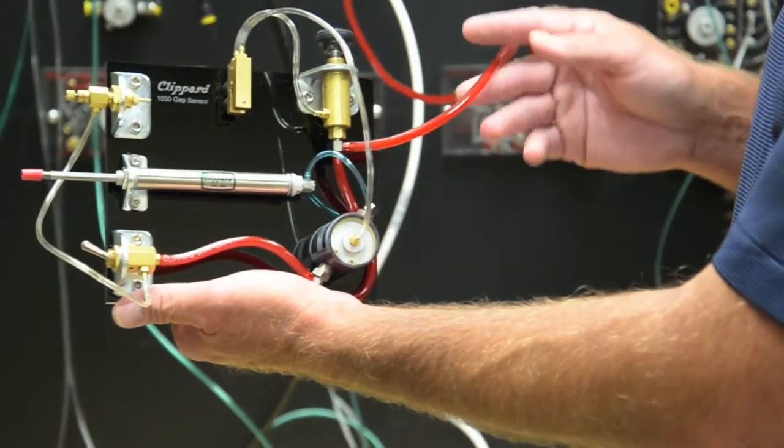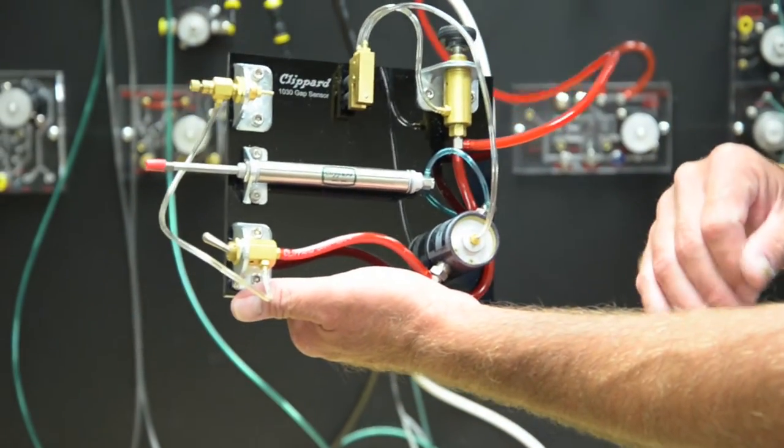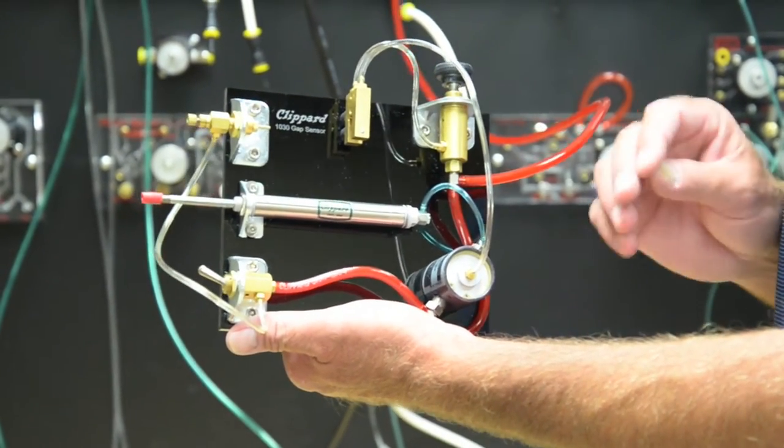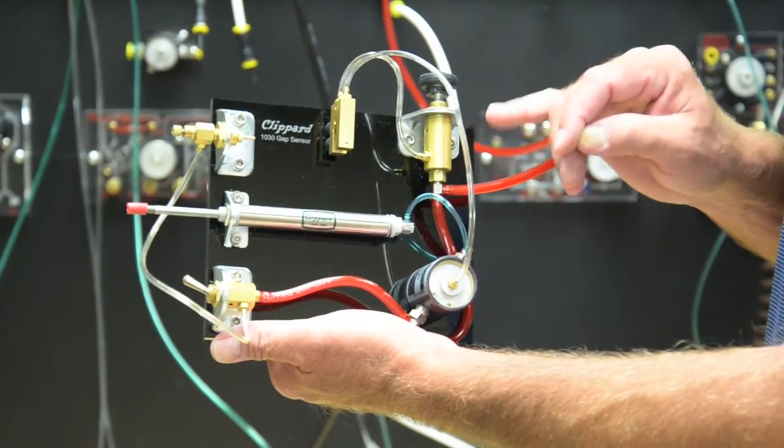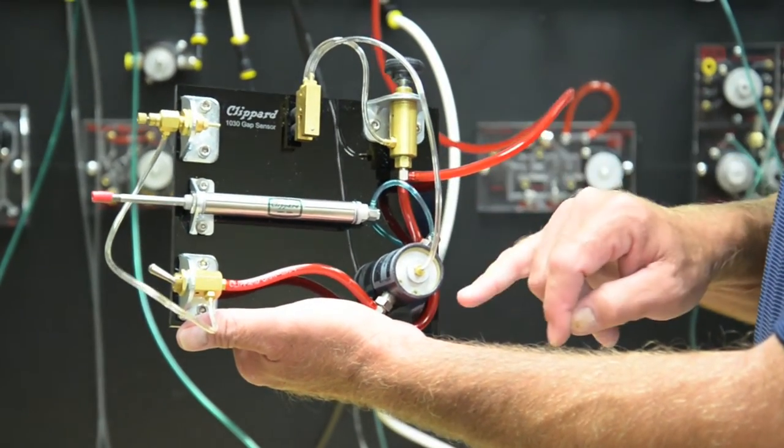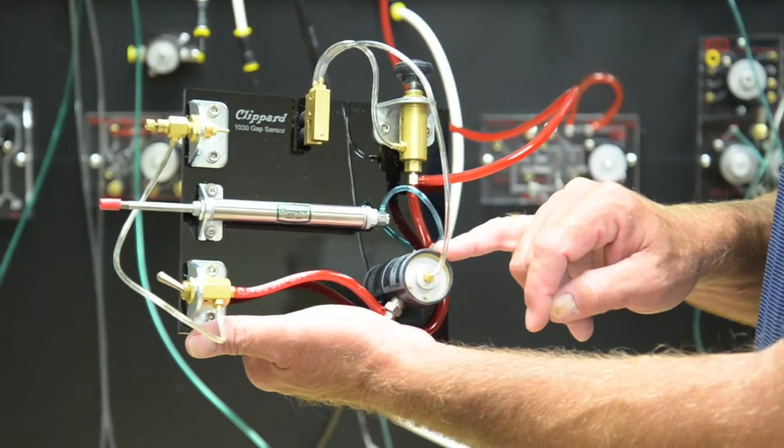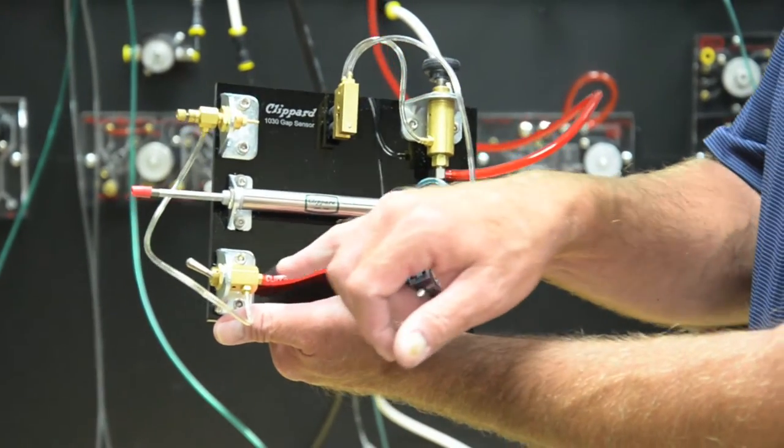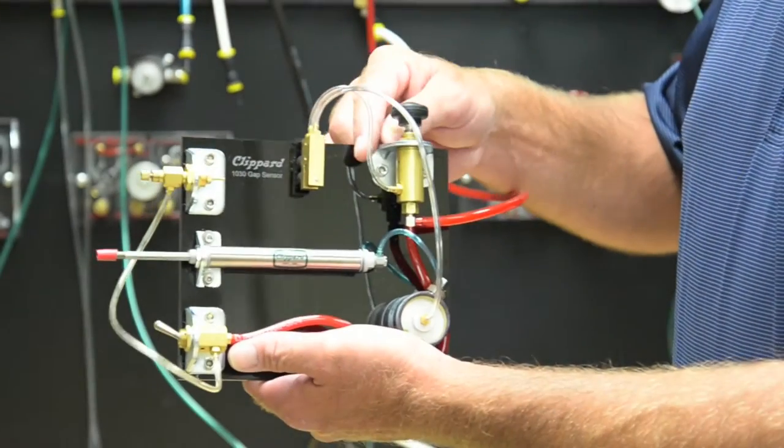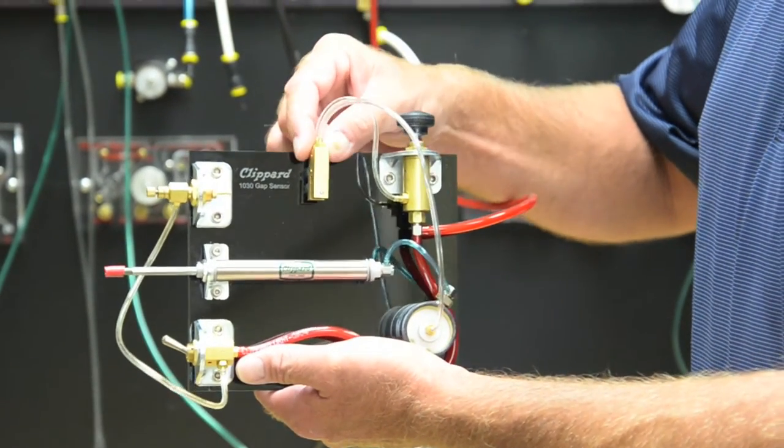Basically what we have is supply pressure coming in to our MAR-1-2 0-20 PSI miniature regulator. Supply pressure also comes down to the 20-10 low pressure control valve and also supplying our TV2 toggle valve. We have the regulator set at approximately 5 PSI going to the 1030 gap sensor.